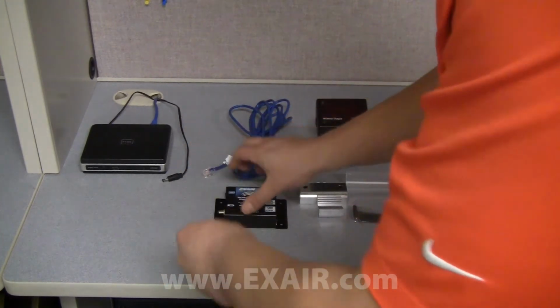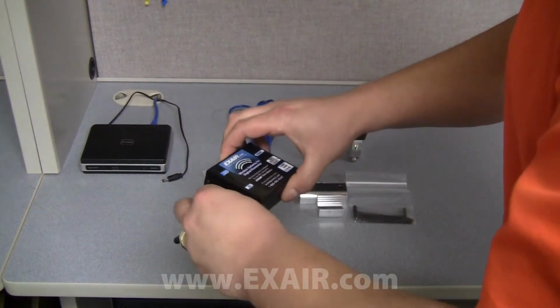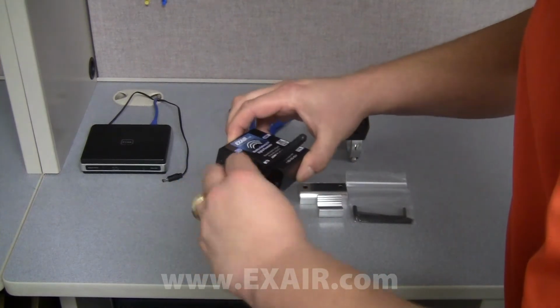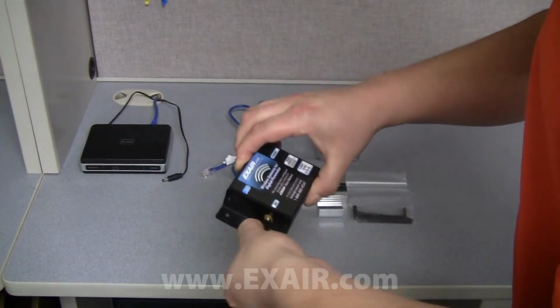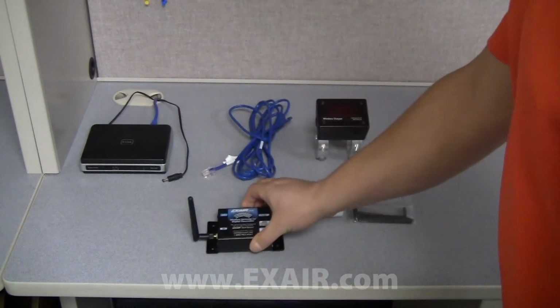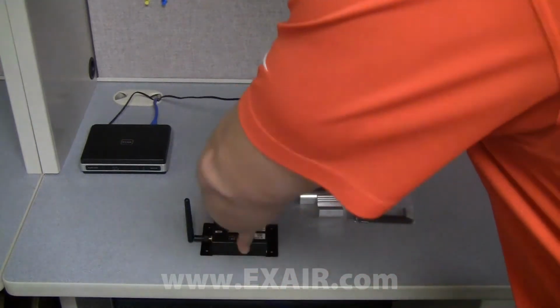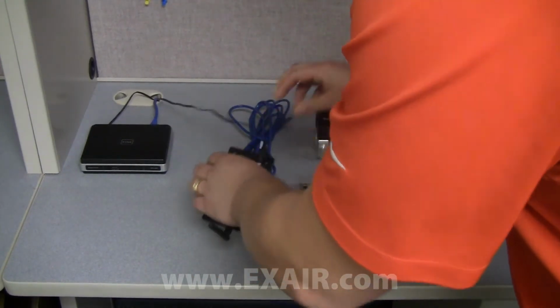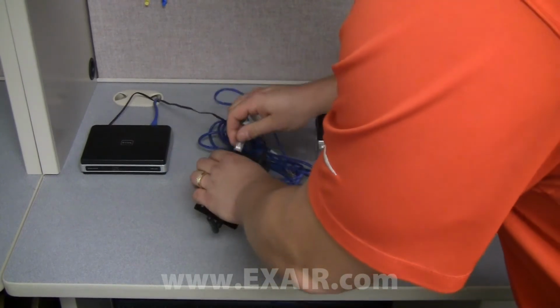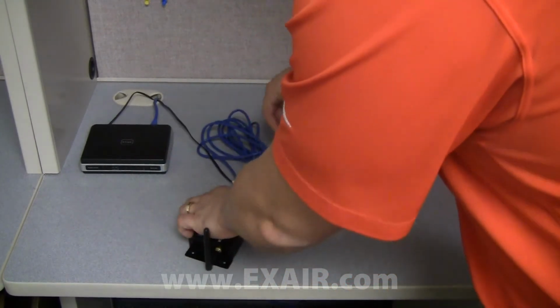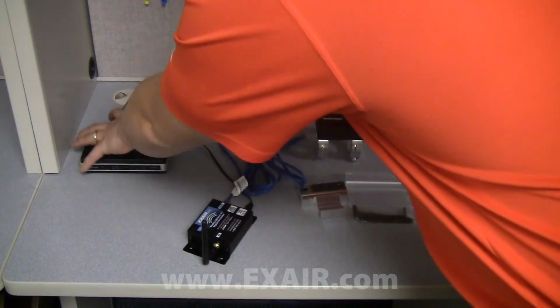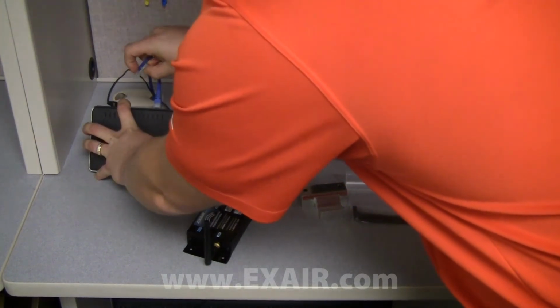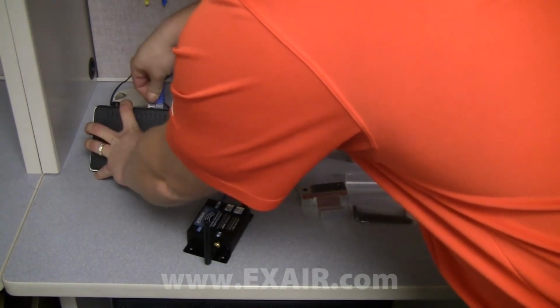After installing the flow meter onto the pipe, remove the gateway from the box and connect the antenna. Then connect the power supply to the right-hand side of the gateway. On the same side as the power supply, connect the Ethernet cable and connect the other end to a LAN connection on a router or switch. Do not connect the gateway directly to a PC.